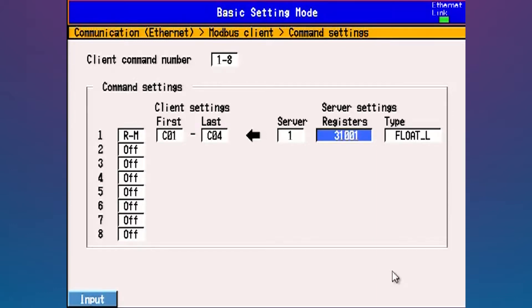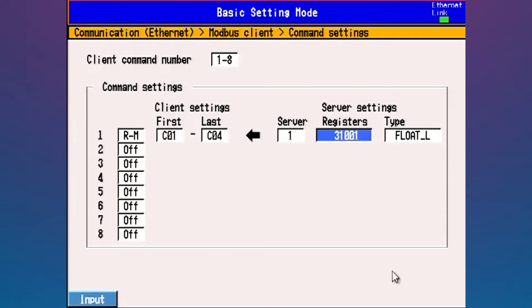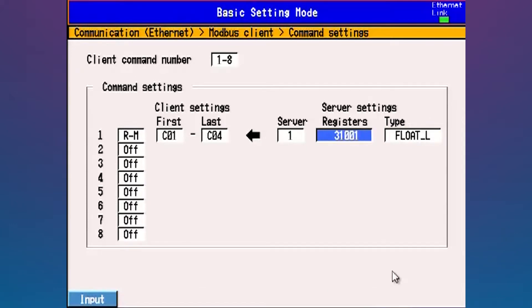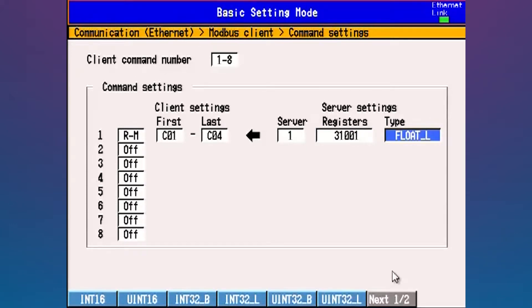If you have an MW100 or a PR300 or some other type of Modbus power meter, in its communications manual it's going to detail all the different registers. In the MW100 communications manual, the Modbus registers for its primary input channels, the floating point versions of those, start at channel 31001. It takes up two registers for every item or channel. In this case, 31001 and 31002 would be used up to bring in the first input channel as a floating point. The same input channels are available as double words, so double integer type data, but in this case I'm just going to bring them in as floating point. That's essentially a decimalized type data.